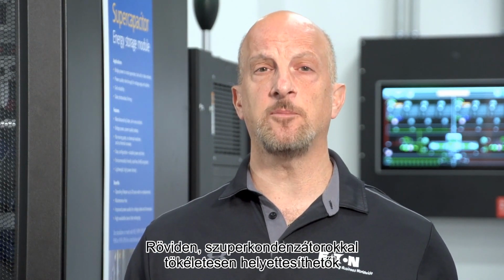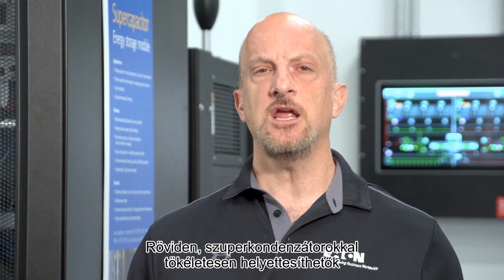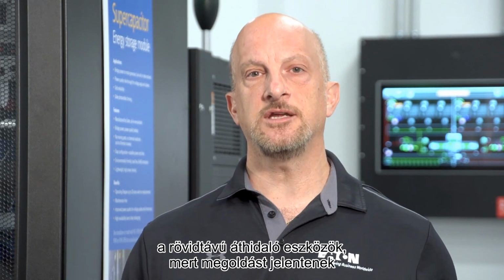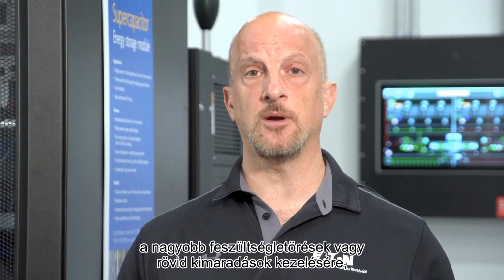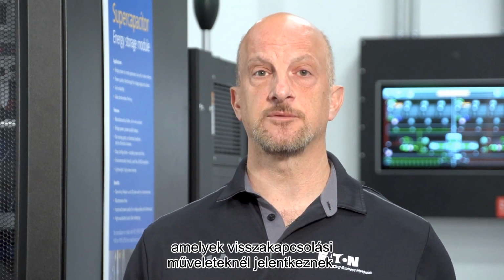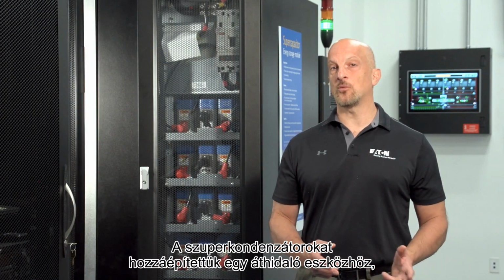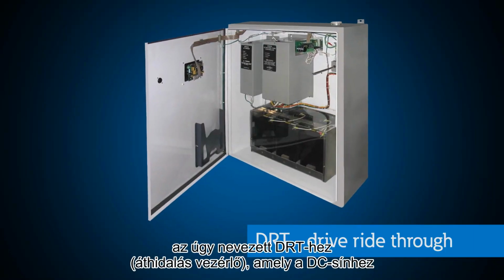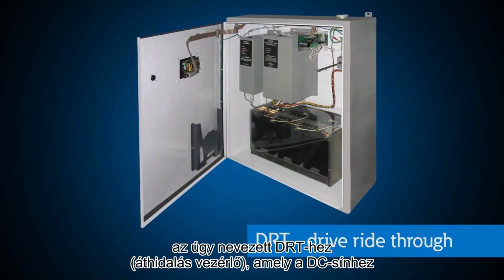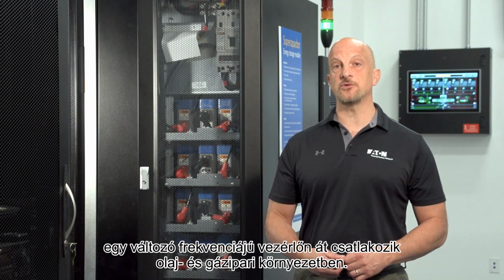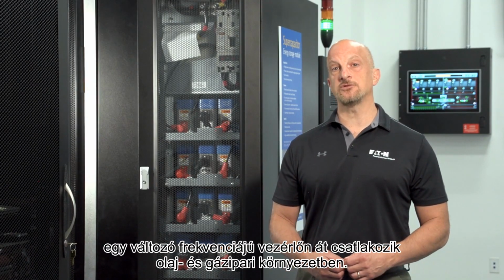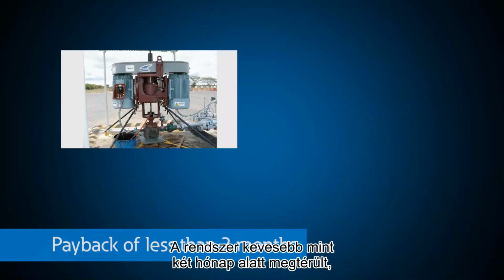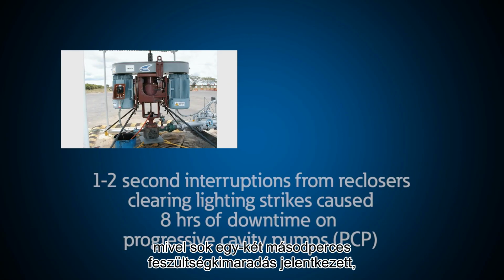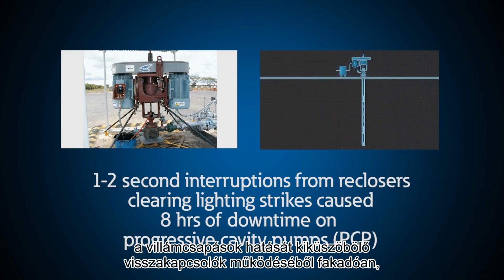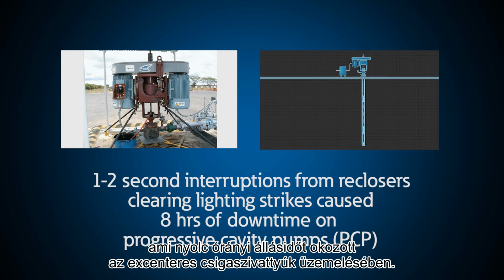In short, supercapacitors are the perfect replacement if you need short-term ride-through to get you through deep sags or short-term interruptions like recloser operations. We put supercapacitors on a ride-through device called a drive ride-through or DRT attached to the DC bus on a variable frequency drive in an oil and gas application. They had a payback of less than 2 months as 1 to 2 second interruptions from reclosers clearing lightning strikes caused 8 hours of downtime on progressive cavity pumps.